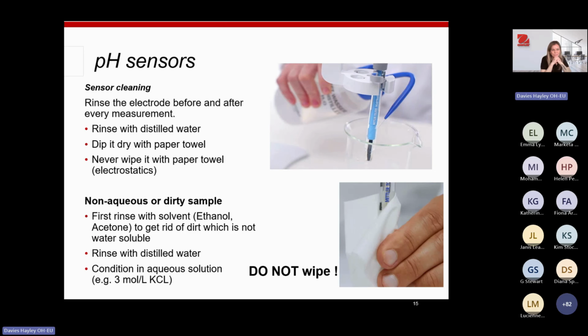pH sensors, so how to clean them. Rinse the electrode before and after every measurement, and before and after every calibration step as well. Always rinse with distilled water. You can use a wash bottle with distilled water and just give it a squeeze over a beaker, and then dab it dry with a paper towel. I don't know why the slide says dip it, apologies. Never rub your electrode, never ever rub, because that would cause static and your readings will be all over the place because you're generating electrostatic charge on the electrode. With a paper towel, all you need to do is just dab it. Again, never rub it and never wipe it, just dab it.